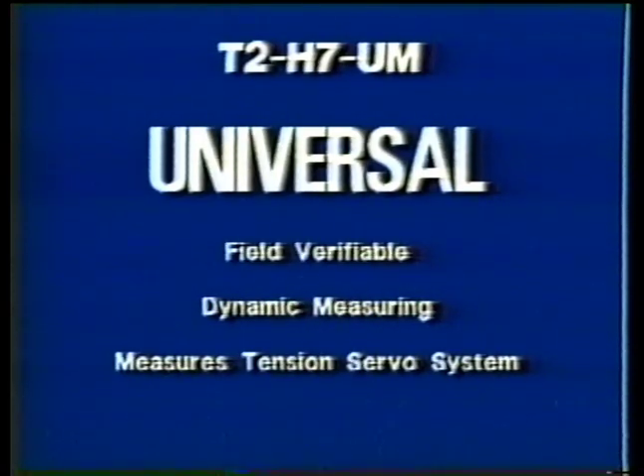The dynamic measuring ability of the tentelometer also allows the entire tension servo system to be easily measured. Low tape tension can result in intermittent video signal, increased video dropouts, intermittent control track and subsequent intermittent picture breakup, skewing errors with video hooking, tape guidance problems and subsequent tape edge damage, intermittent audio, and other causes of tape destruction. High tape tension can cause skewing errors with video hooking, premature video head tip wear, tape edge damage due to high tape tension at guides, and tape destruction due to stretching at high stall tensions.